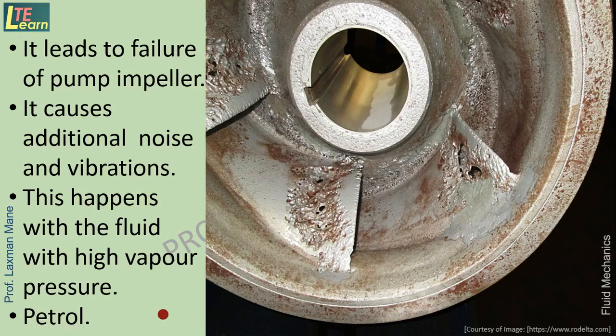So from this we can understand that when we are going to design a pump as per the type of fluid, it may be water or petrol, we have to take care that inside the pump the pressure at the pump casing should not fall below the vapor pressure of the fluid for which we are going to use that pump.